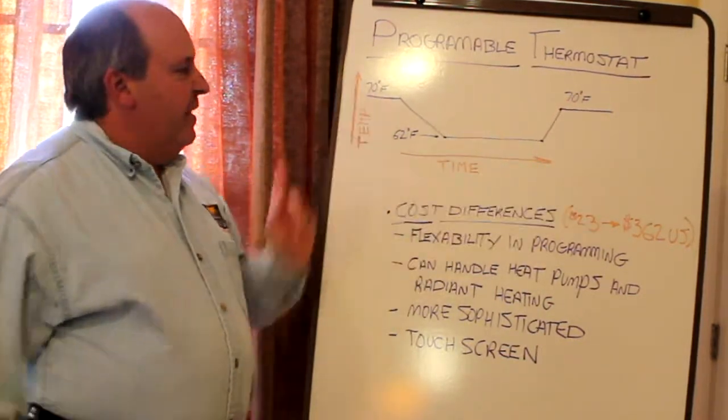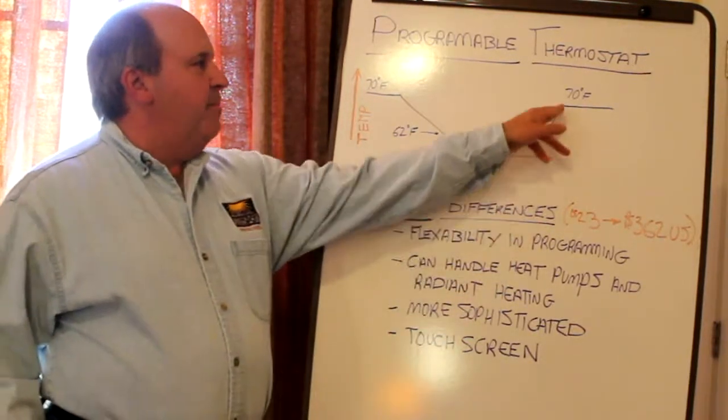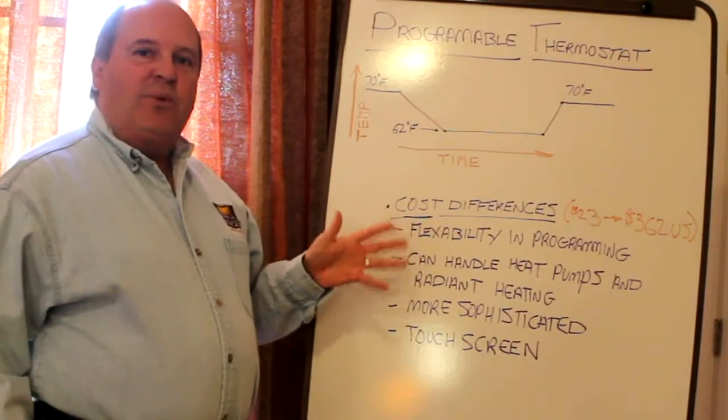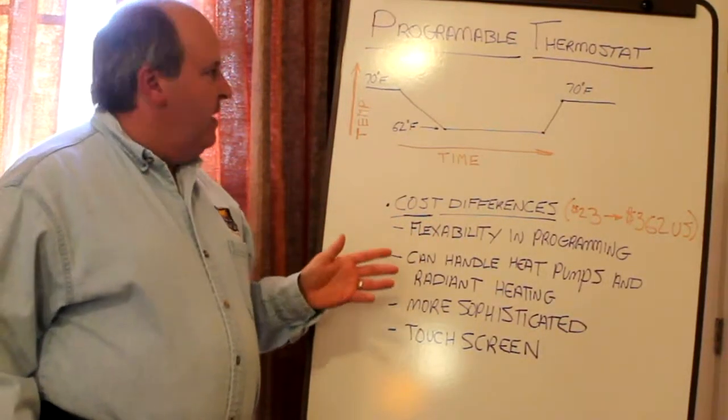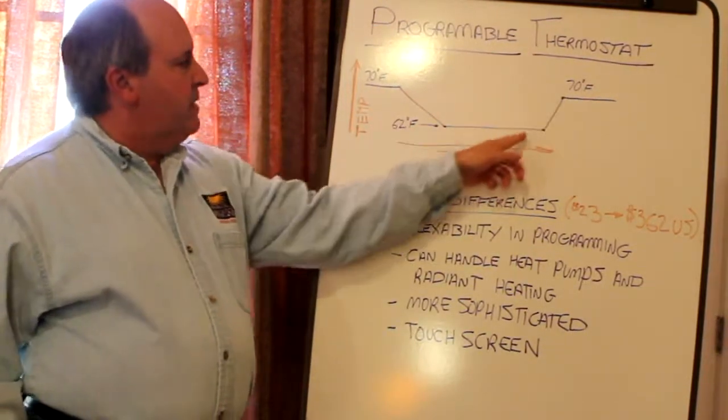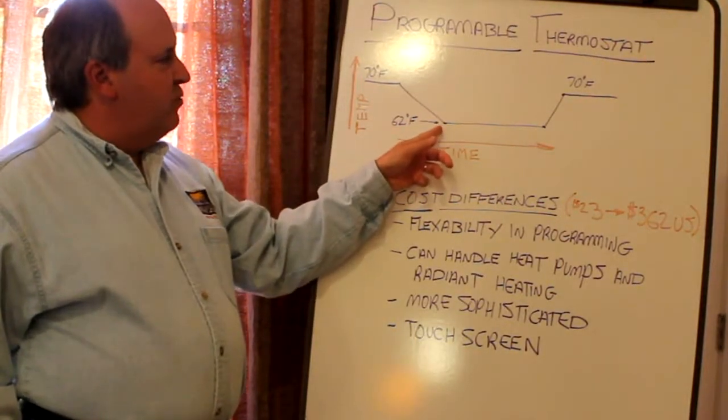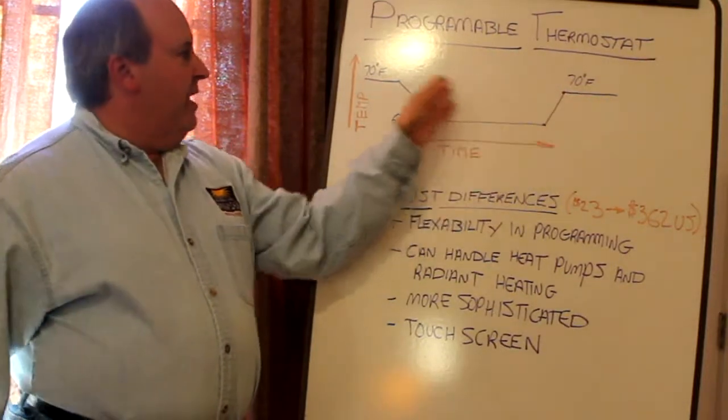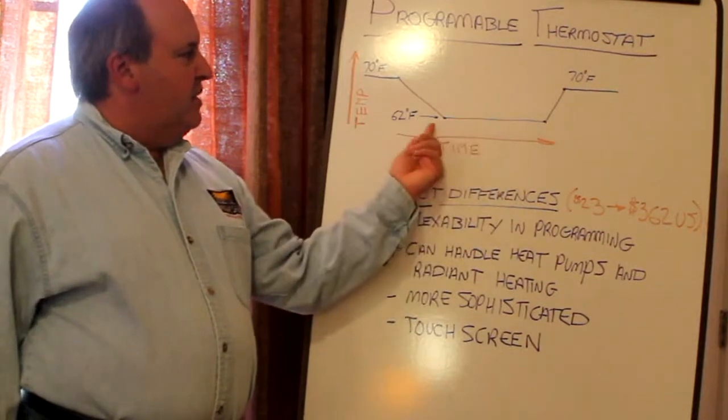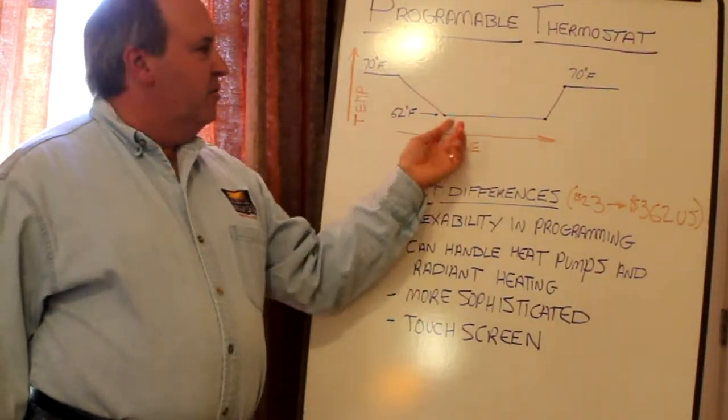So this is time here and this is temperature here. Now some folks will argue that well that isn't worth doing because this heat up piece that has to bring the temperature back up wastes a lot of energy so I really don't save anything. Well the research shows that the energy that's saved during the drop is equal to the energy used during the warm-up. The good news is for as long as it's 62 degrees, 8 degrees cooler, you're saving a lot of energy.